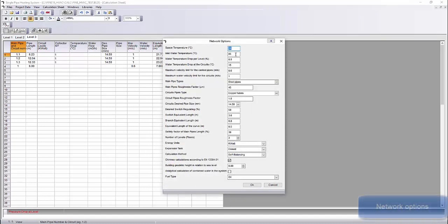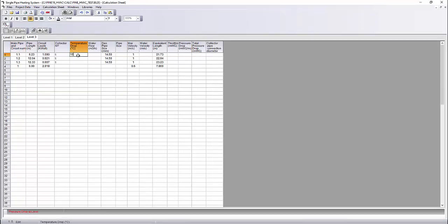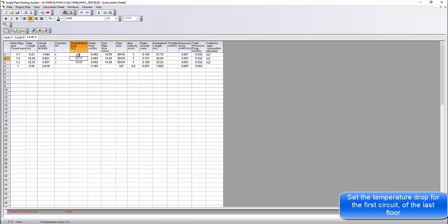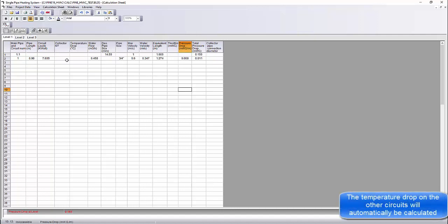On the network options menu, we can see the basic parameters such as the water temperature, the pipe types, the desired pipe size, the calculation method, etc. In order to calculate the temperature drop, for the self-balancing method we need to define the temperature drop for the first circuit of the last floor. When that temperature is defined, all the calculations will be done.